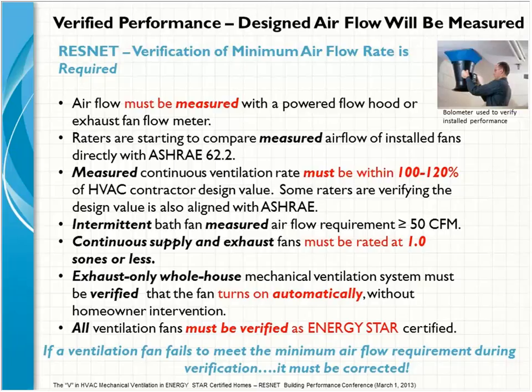It's important that now it be tested, and our HERS raters are the people who will most likely be doing that. You see the picture of the gentleman in the top right-hand corner. They're holding a flow meter. That's a device that measures airflow in two directions and gives a readout so that the rater can put that into his report and verify that the fan is testing at the minimums to meet the code. And we want to keep those measurements, or that airflow calculation performance, between 100 and 120%.